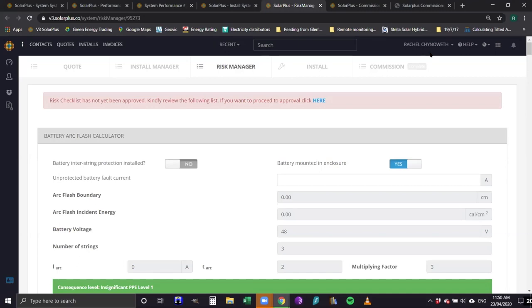Moving on to commissioning — there is a risk management page where you can do your arc flash calculation for batteries, and a checklist of risk assessment that picks up the specific battery you've chosen and the battery chemistry. It's system-specific for your design for this quote. Can we include the grid protection board in an SLD, including secondary protection requirements for commercial? There is a box for grid protection. The thing with the line diagram and the system manual is that you can edit it in a third-party PDF editor and change your line diagram or add boxes to it yourself.